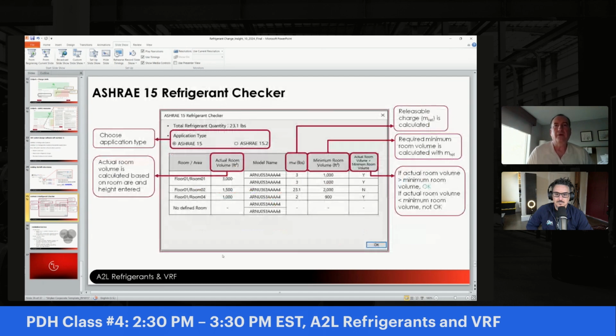And then we will have a refrigerant checker built in. This will check the refrigerant and the room volume for you. So after you get all your information input into this—models, pipe lengths, whether you have a valve kit or not, room information—you then run this refrigerant checker based on the calculations for ASHRAE 15.